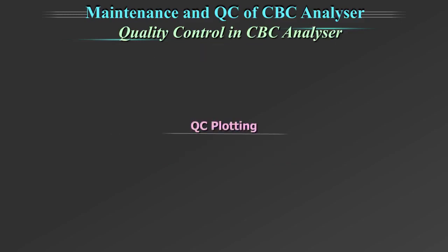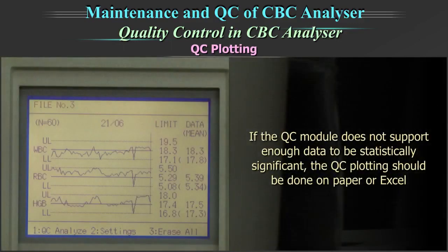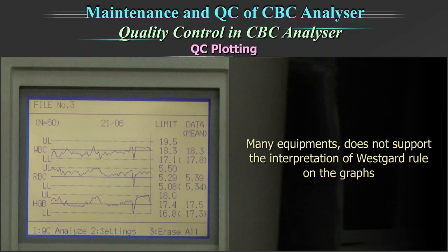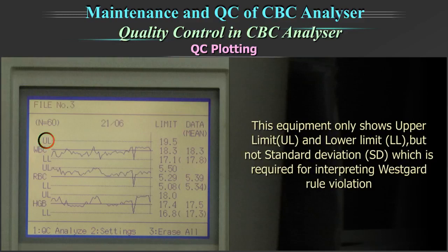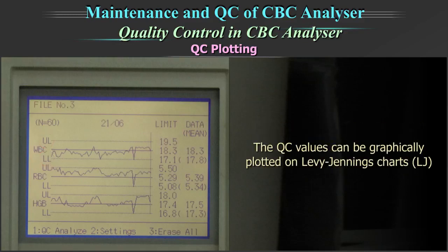The quality control plotting. If the quality control module does not support enough data to be statistically significant, the quality control plotting should be done on paper or Excel sheet. Many equipments, including this one, do not support the interpretation of Westgard rules on the graph. This equipment only shows upper limit, that is UL, and lower limit, that is LL, but not the standard deviation, which is required for interpreting Westgard rule violation. The quality control value can be graphically plotted on the Levy-Jennings chart.